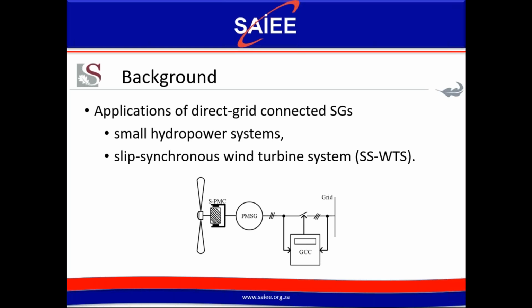The slip synchronous wind turbine system consists of fixed speed turbine blades, which is connected to a slip permanent magnetic coupling, or SPMC, which itself is connected to a conventional permanent magnet synchronous generator, or PMSG. The slip synchronous wind turbine system is directly connected to the grid by means of a grid connection controller. It should be noted that once grid connected, power flows directly from the generator to the grid without first flowing through the grid connection controller, or GCC.